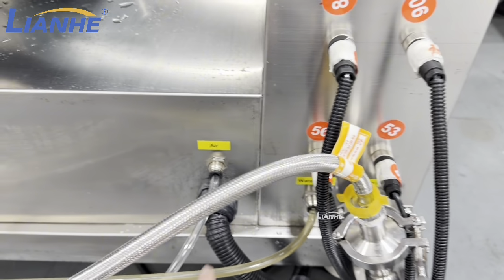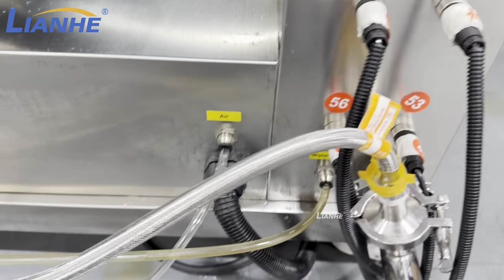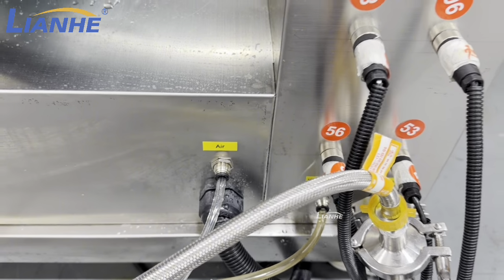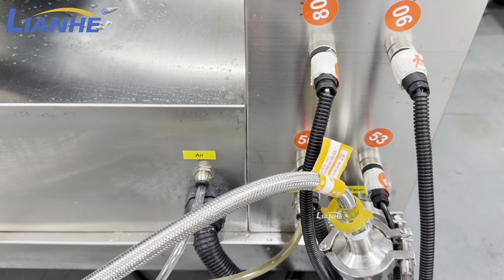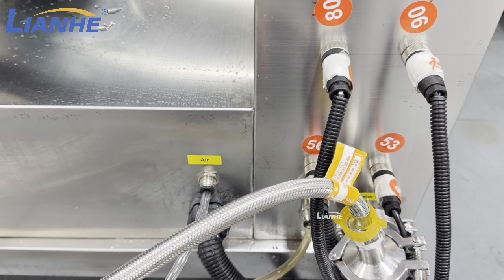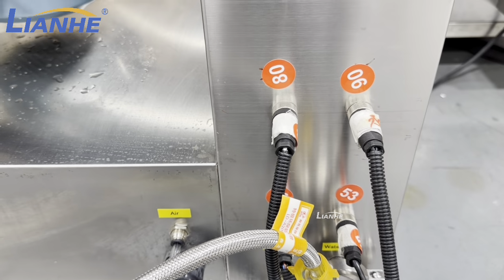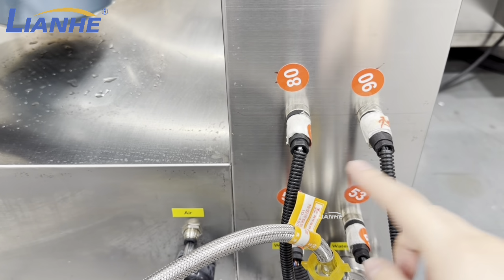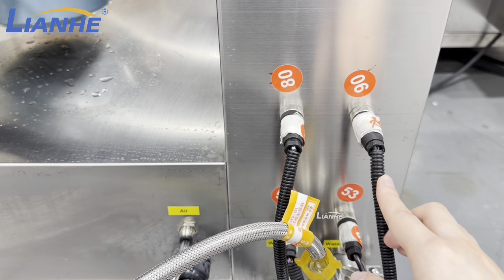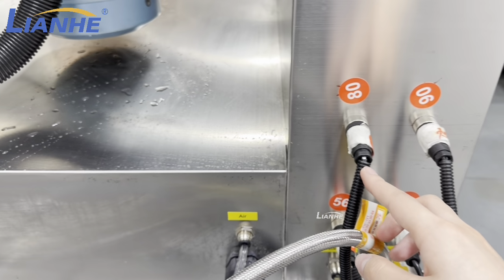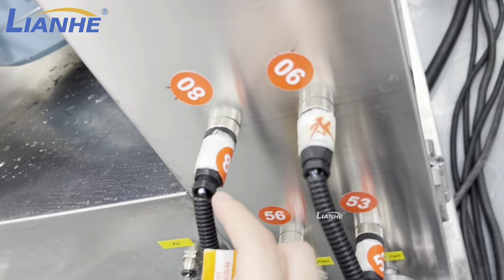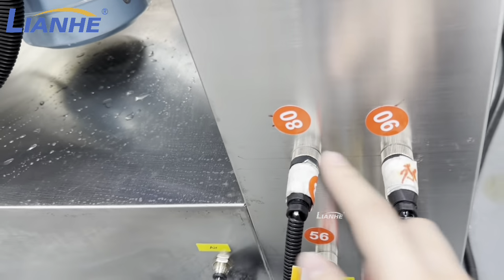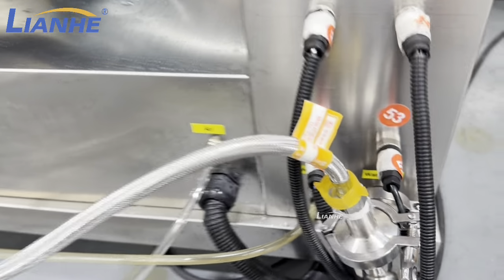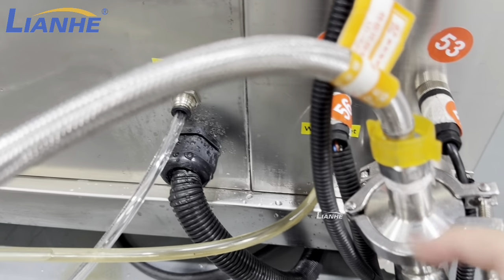Here we have the air inlet. You should connect to your compressed air to make sure that you can use the pneumatic bottom valve. And also here we have the wires. We have marked the numbers on it. You should connect it according to the same number. Here the 8 connect to 8, 6 connect to 6. And then also here is the same.